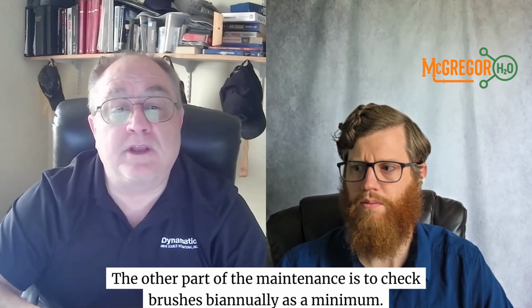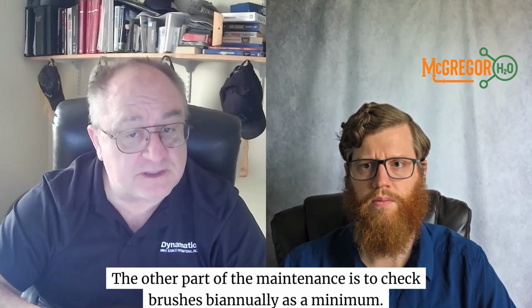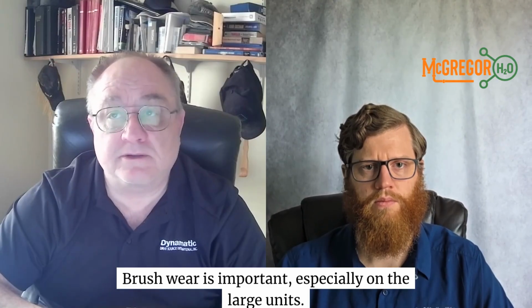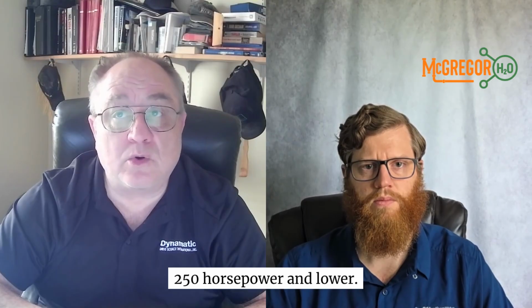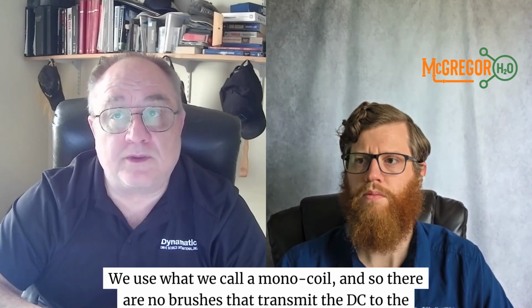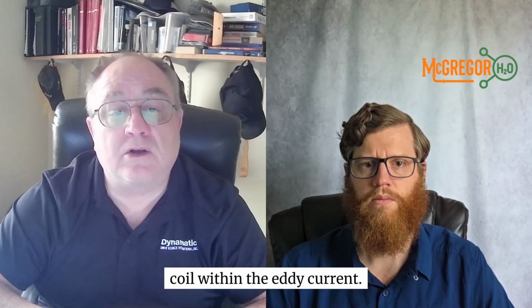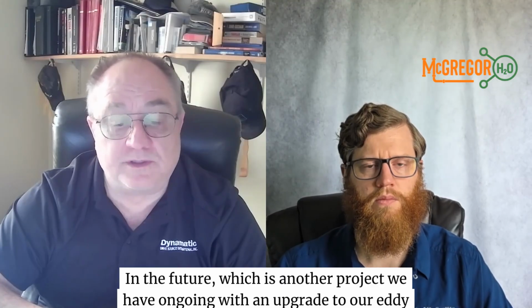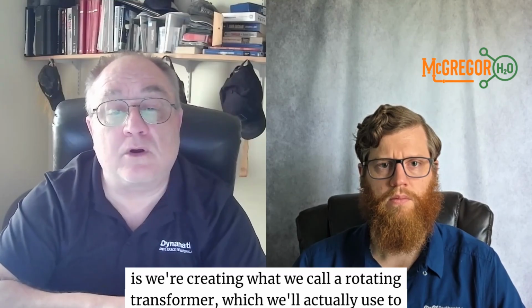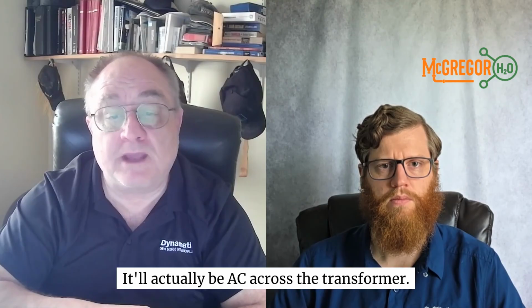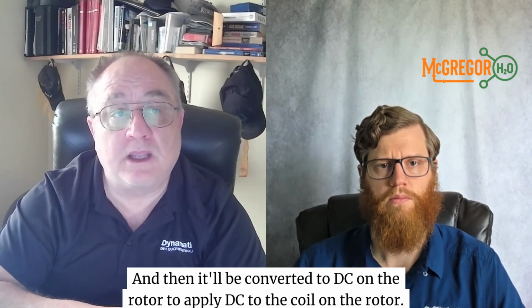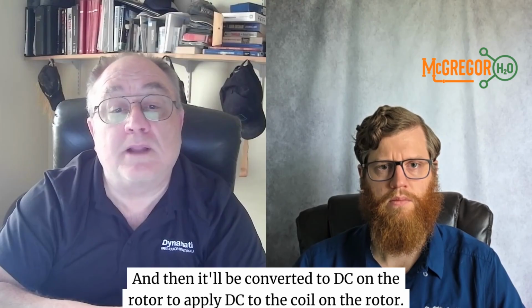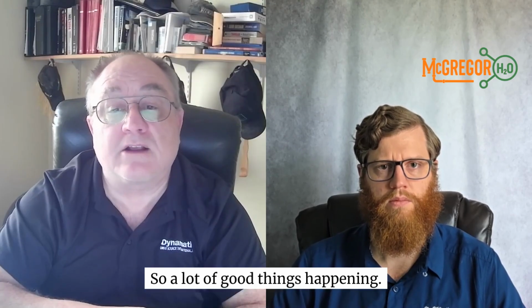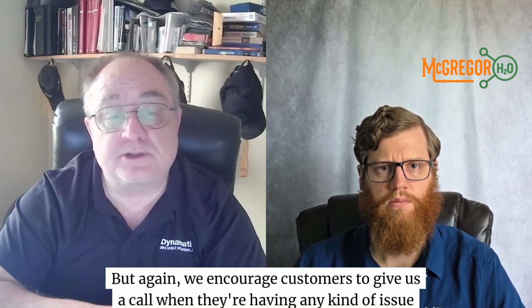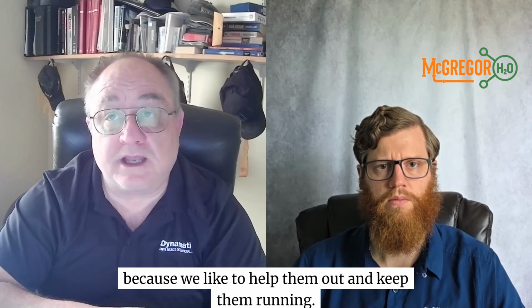The other part of the maintenance is to check brushes biannually as a minimum. Brush wear is important, especially on the large units, 250 horsepower and lower. We use what we call a monocoil, and so there are no brushes that transmit the DC to the coil within the eddy current. In the future, which is another project we have ongoing with an upgrade to our eddy current drives, we're creating what we call a rotating transformer. It'll actually be AC across the transformer, and then it'll be converted to DC on the rotor to apply DC to the coil on the rotor. So a lot of good things happening. But again, we encourage customers to give us a call when they're having any kind of issue because we like to help them out and keep them running.